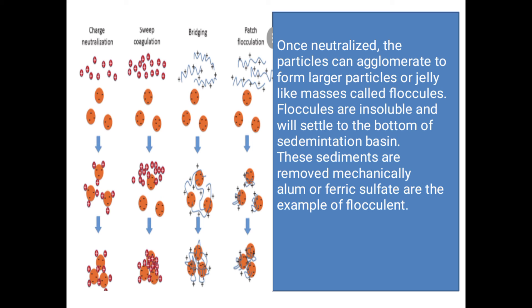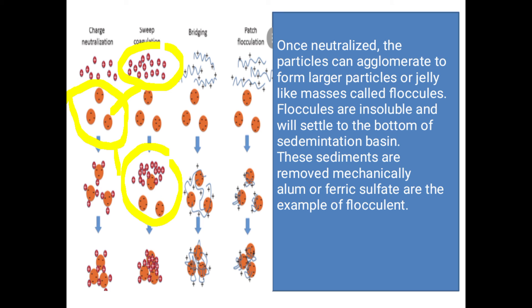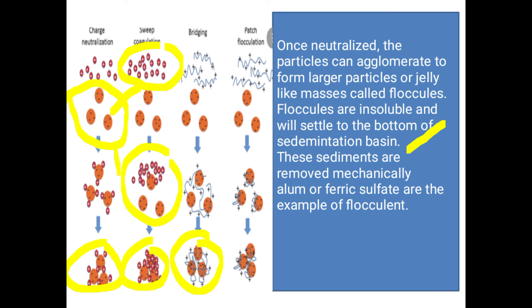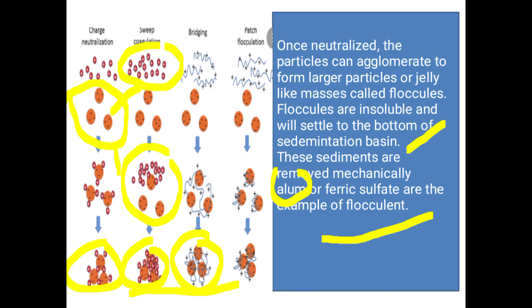Once we add positively charged flocculants, they neutralize the negatively charged particles. When they neutralize each other, they form larger, gel-like masses called flocs. Flocs are insoluble and will settle to the bottom of the sedimentation tank. These sediments are then removed mechanically. The most important flocculants are alum, or ferric sulfate, which are examples of flocculants that drive flocculation.